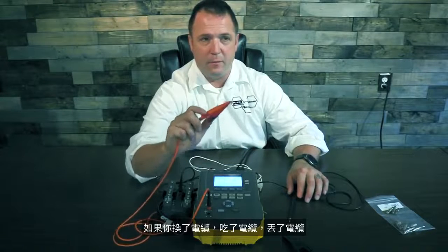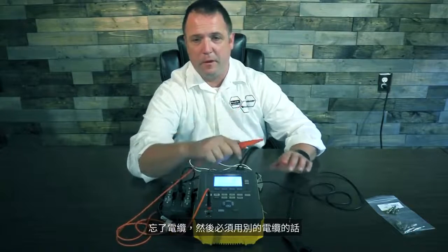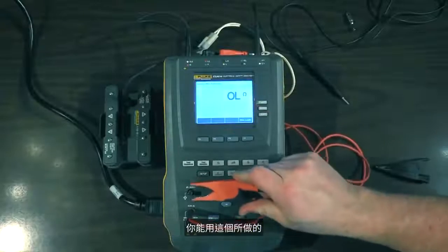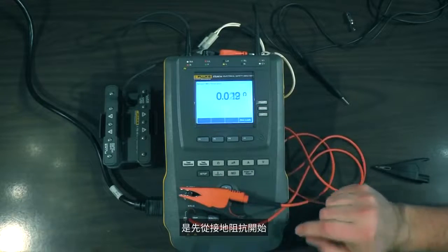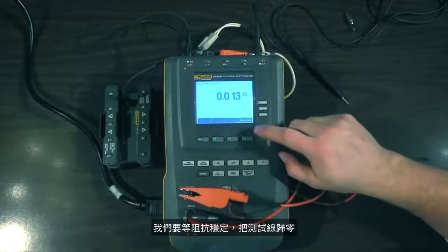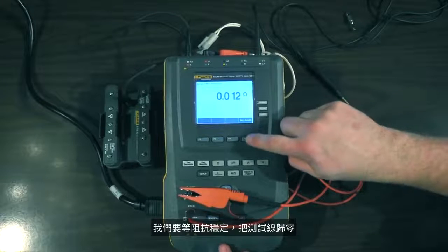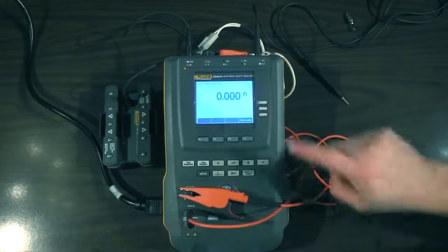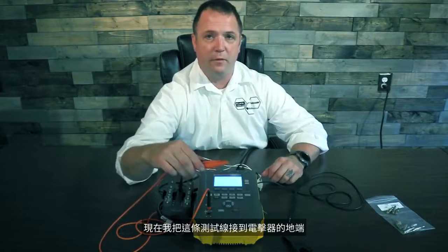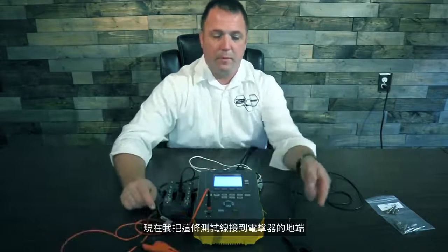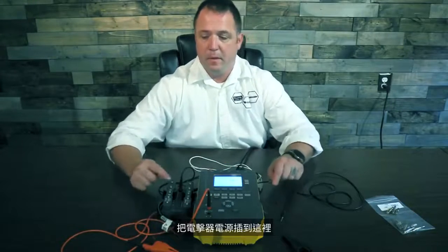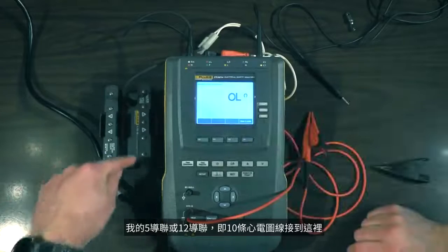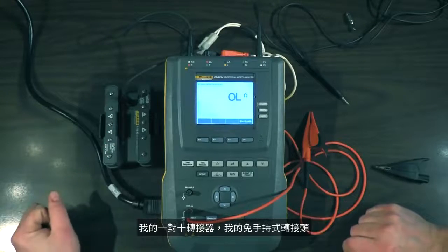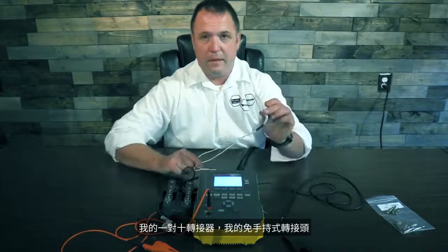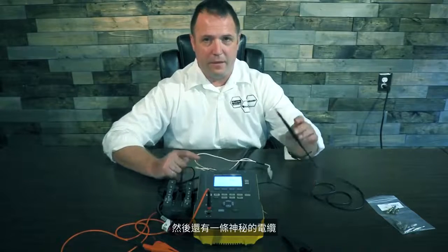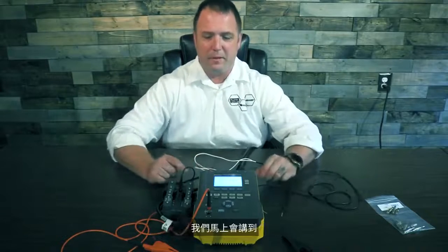If you've changed the cable, ate the cable, lost the cable, forgot the cable, and had to use some other cable, what you can do with this, we'll start off by going to the ground. We're going to ground wire resistance. And we're going to zero our cable out. Now I'll take this to the ground stud of the defibrillator. Plug the defibrillator into here. My 5-lead or 12-lead, which is 10 wires, ECG over to here. My 1 to 10 adapter. My hands-free adapter here. And then this other mystery cable that we'll cover here in a second.